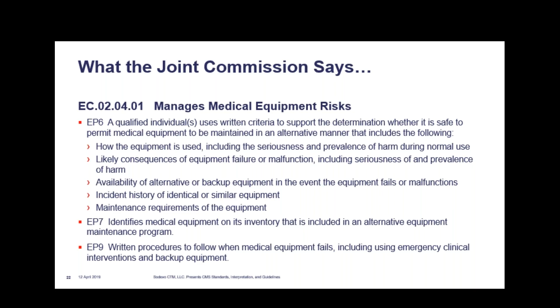In CMS's guidelines for this, they actually call out interval based. So if anybody takes care of beds, have a hard time finding beds, your risk assessment can tell you that your bed frequency can be between 12 and 24 months if you've risk ranked it and can prove it. So you can check it anytime in the next year to 2 years. Identify medical equipment on the inventory that is included in the AEM, and a written procedure to follow if medical equipment fails, including emergency medical intervention and backup. Intervention is more on the clinical side than what we do. We provide solutions though.